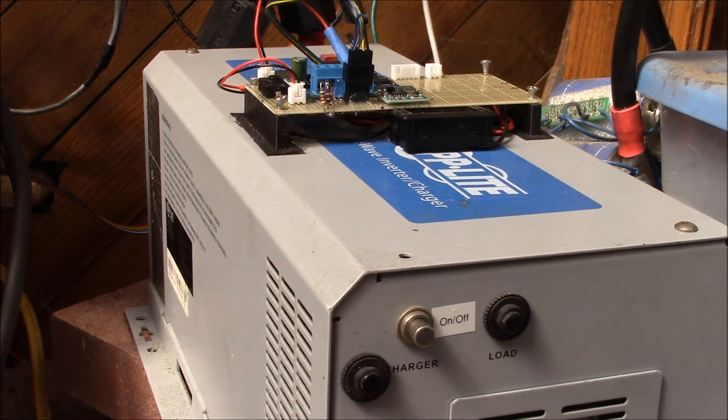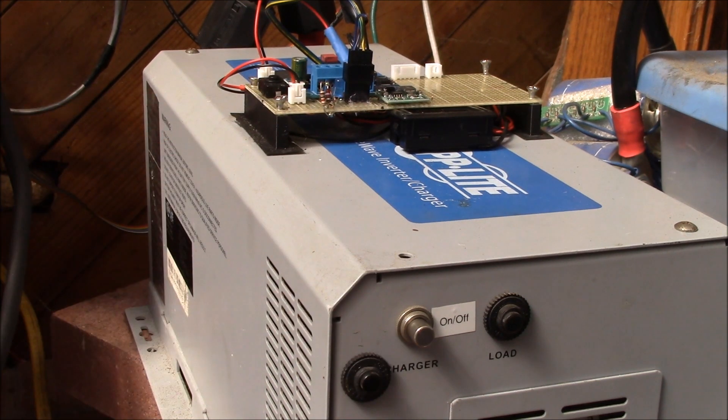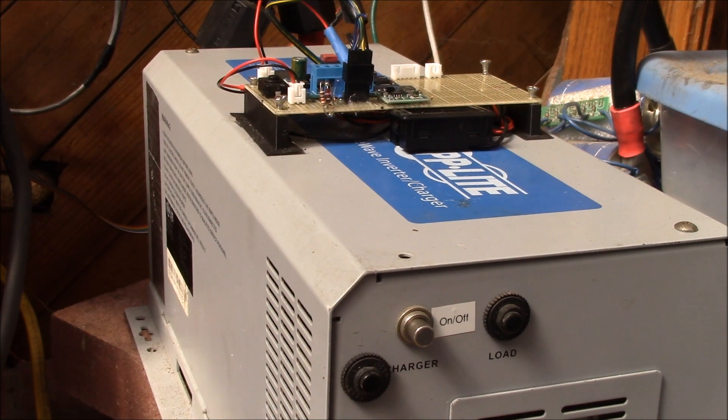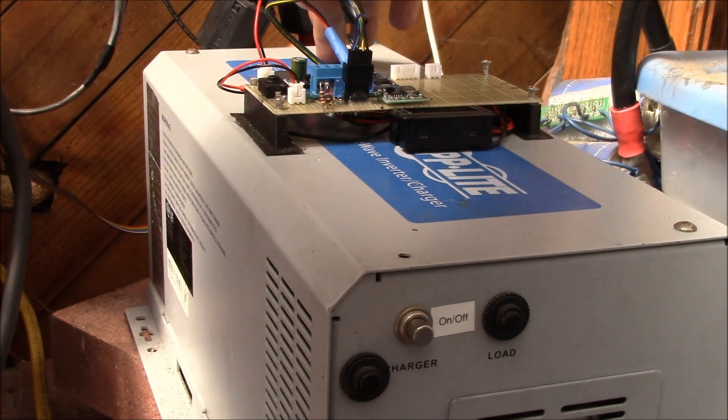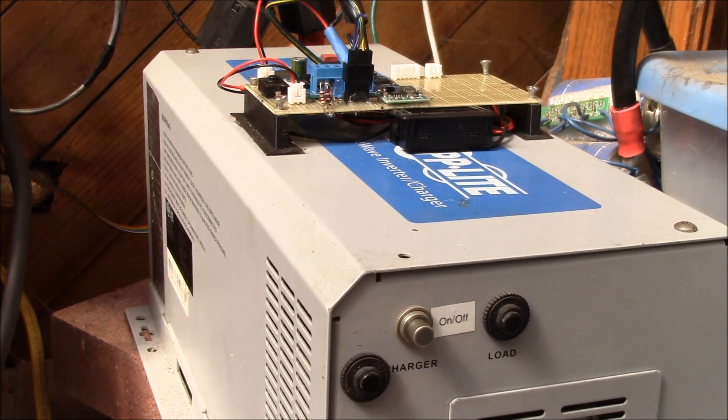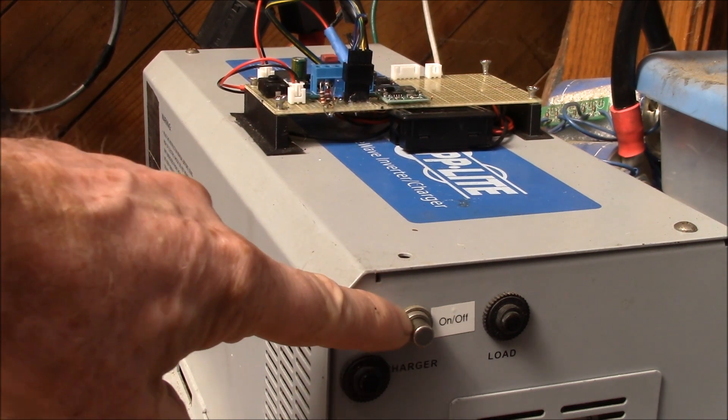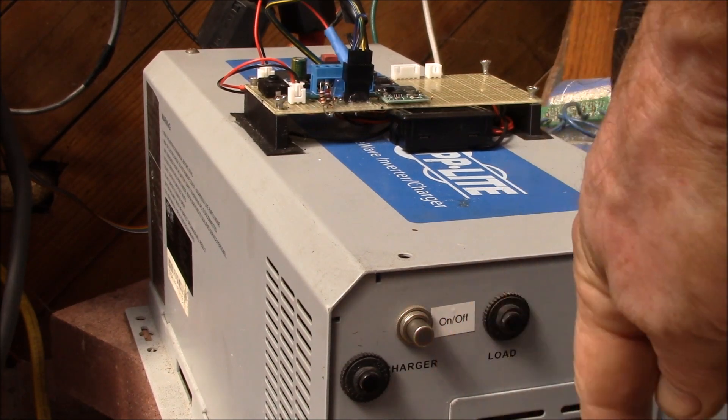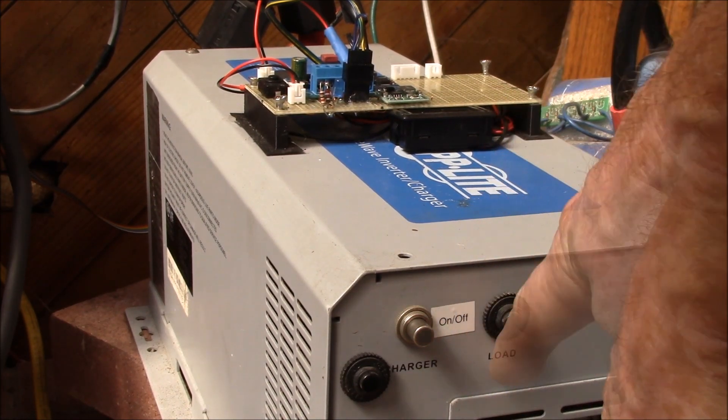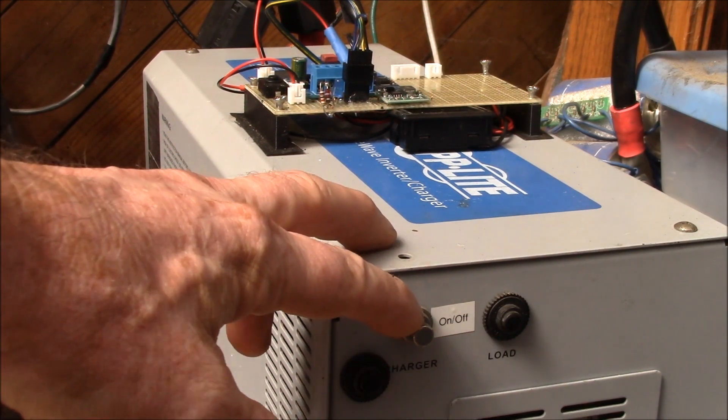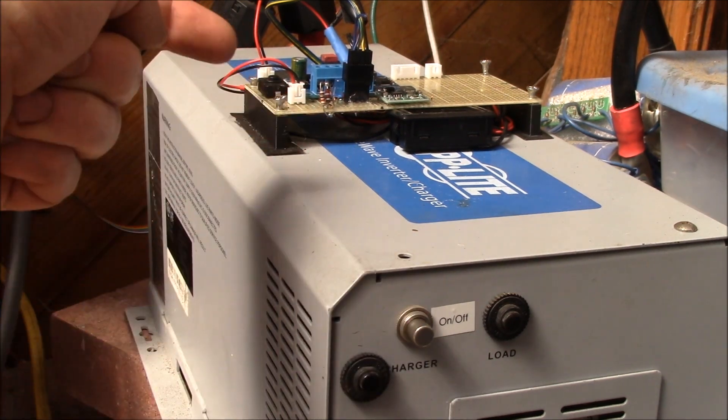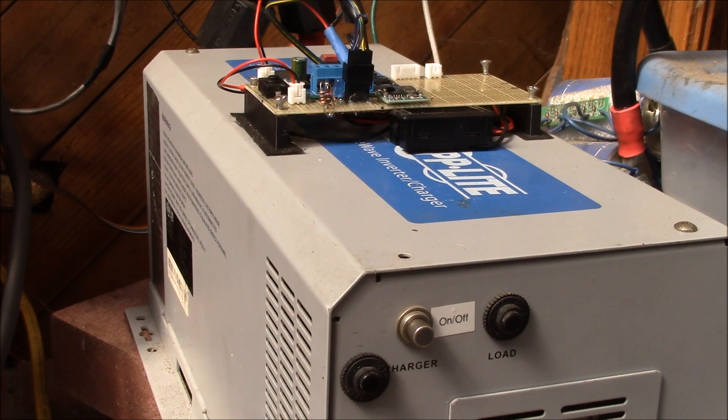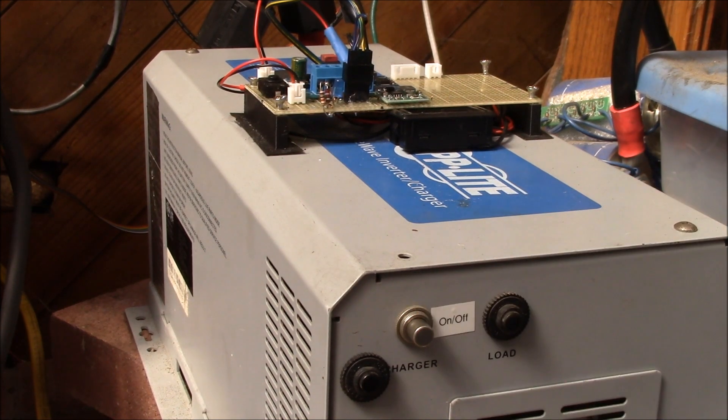Let me go up here and try to turn on the inverter. I can turn it on and everything's fine, it's still running on the AC power. But if there were now a power failure - I'm going to unplug the inverter from the wall - and it doesn't like that. What I have to do is close the breaker and then reset it. Now it's running because it won't go into UPS mode if that breaker's open. It's in the line between the incoming power and the transformer, but that's the same circuit that gets used when you're taking battery power and inverting it into AC power.